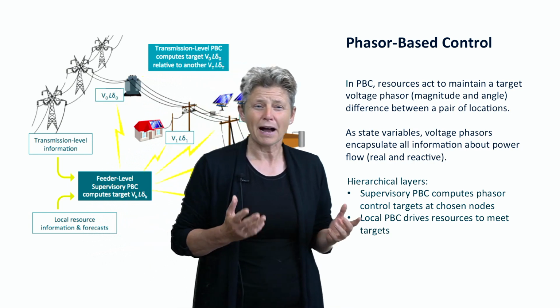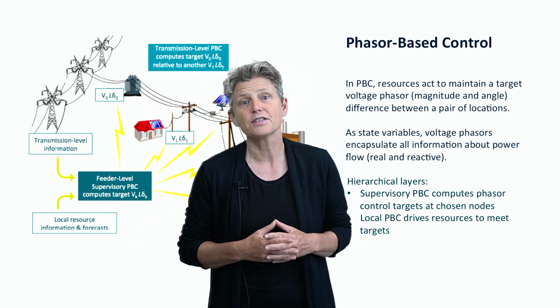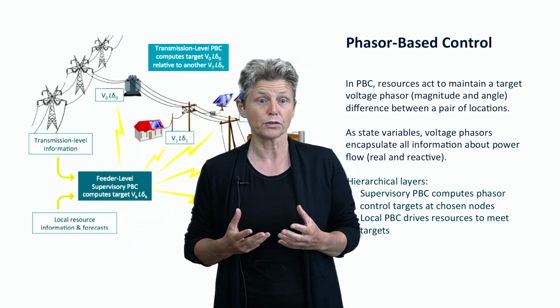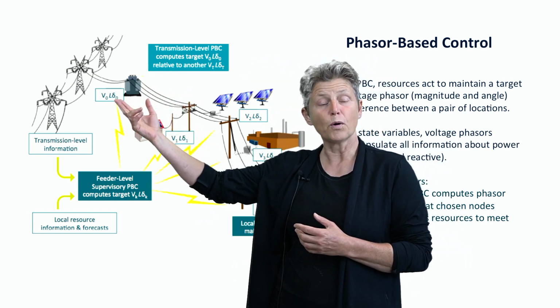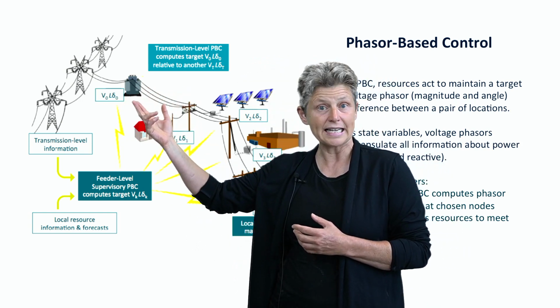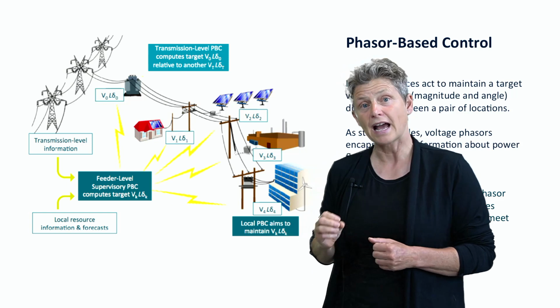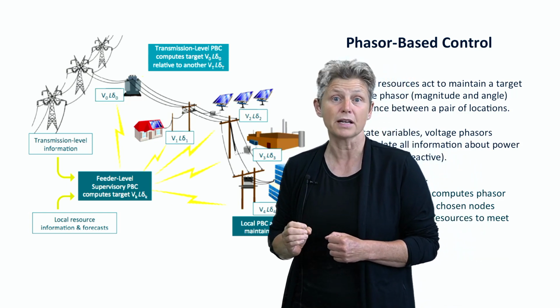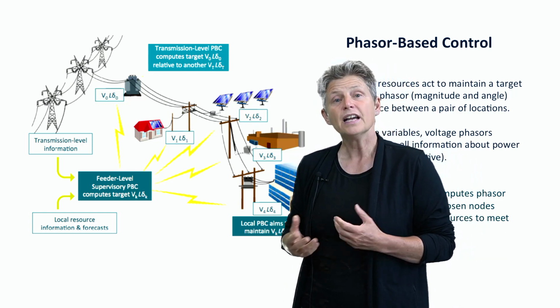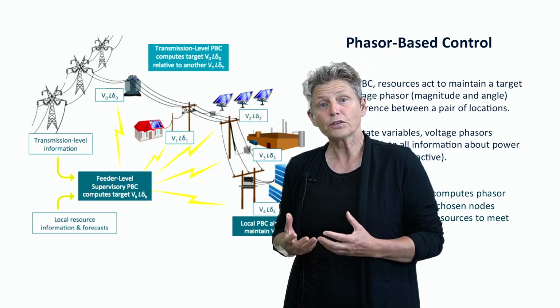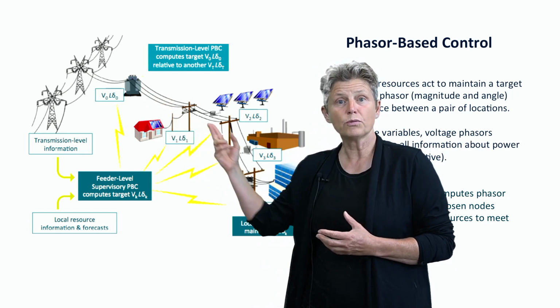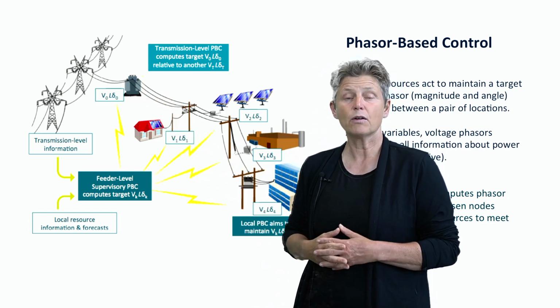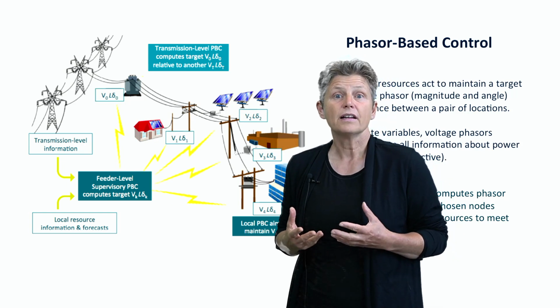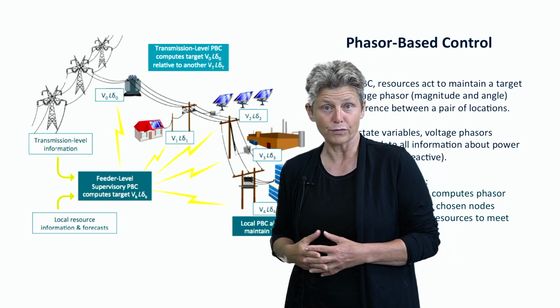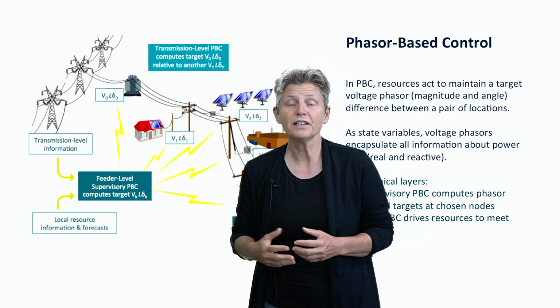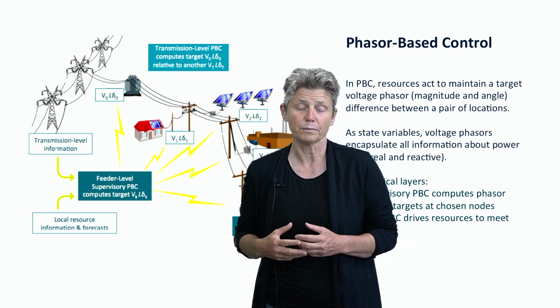The entire power flow situation here is articulated in terms of voltage phasors. Those would be voltage magnitudes, V, and angles, delta, referring to the precise timing of the voltage waveform. Together, the voltage phasors at each node in an AC network define everything there is to know about power flow. They define real and reactive power flow.